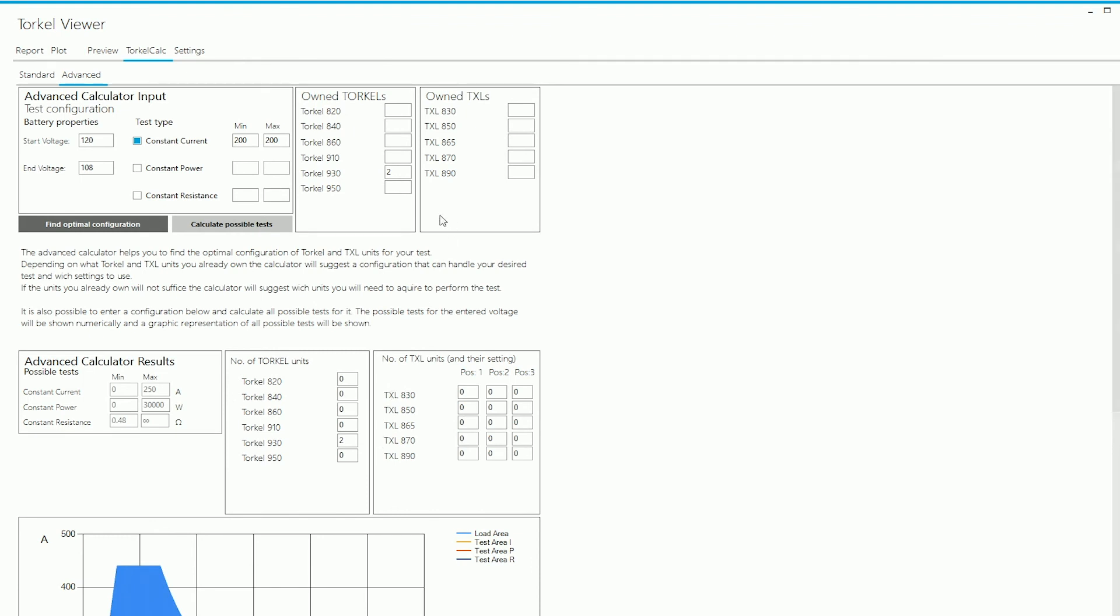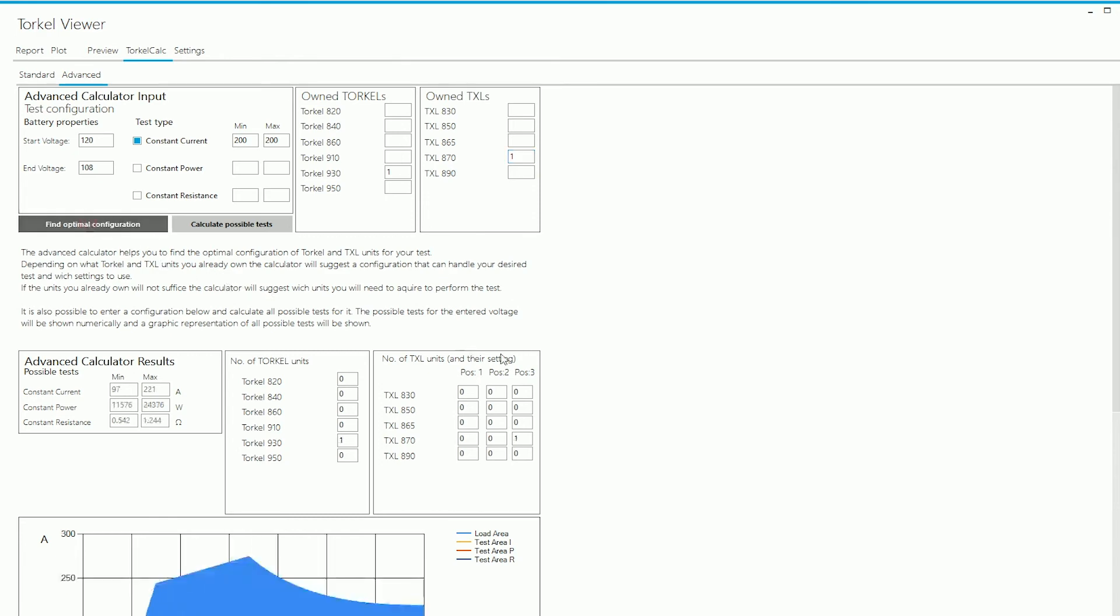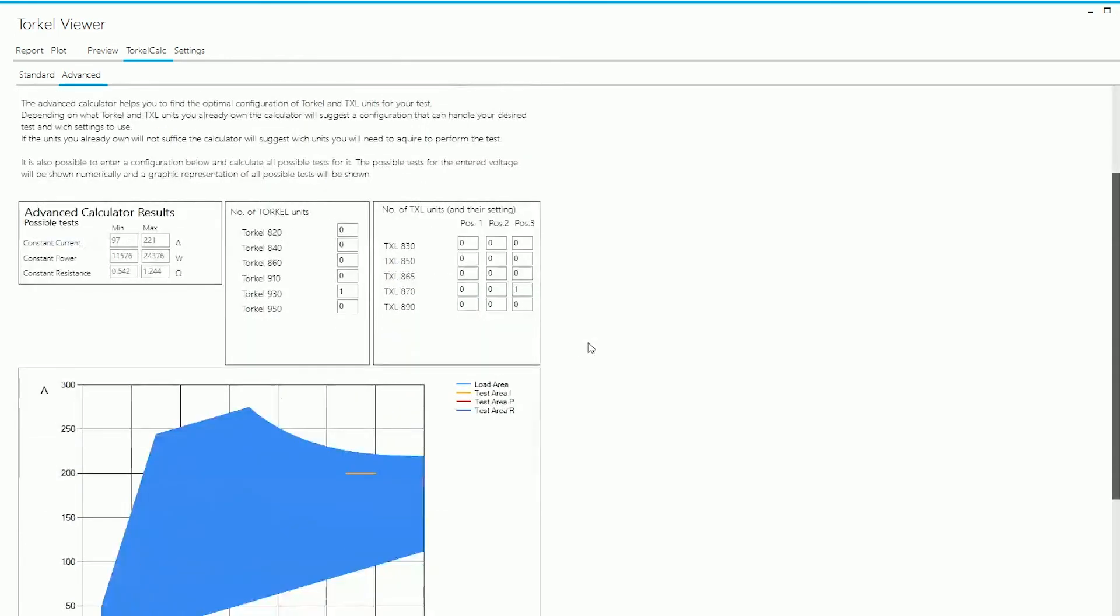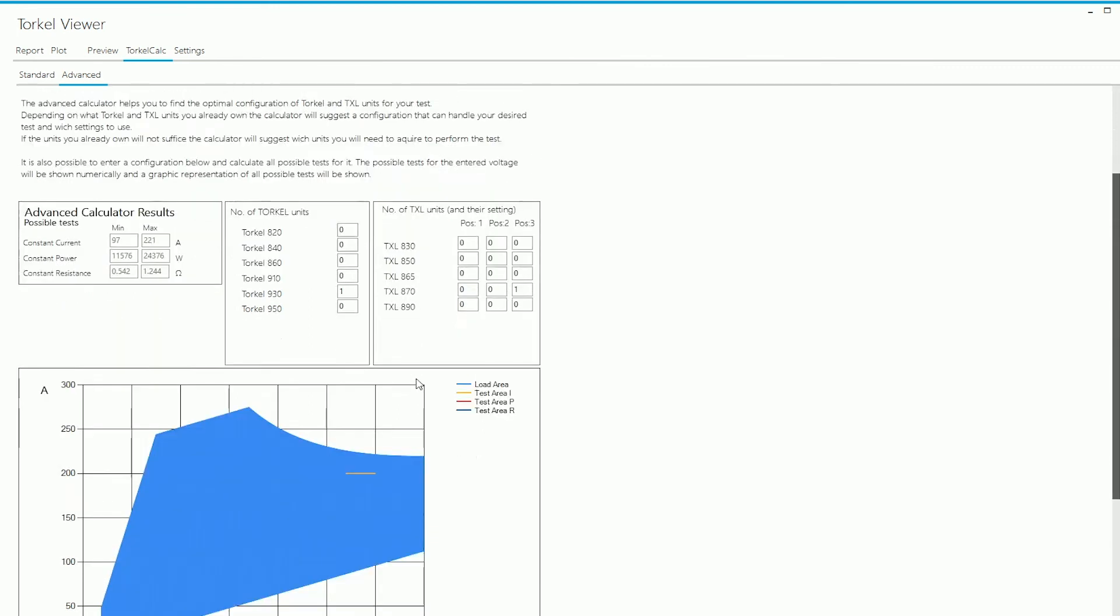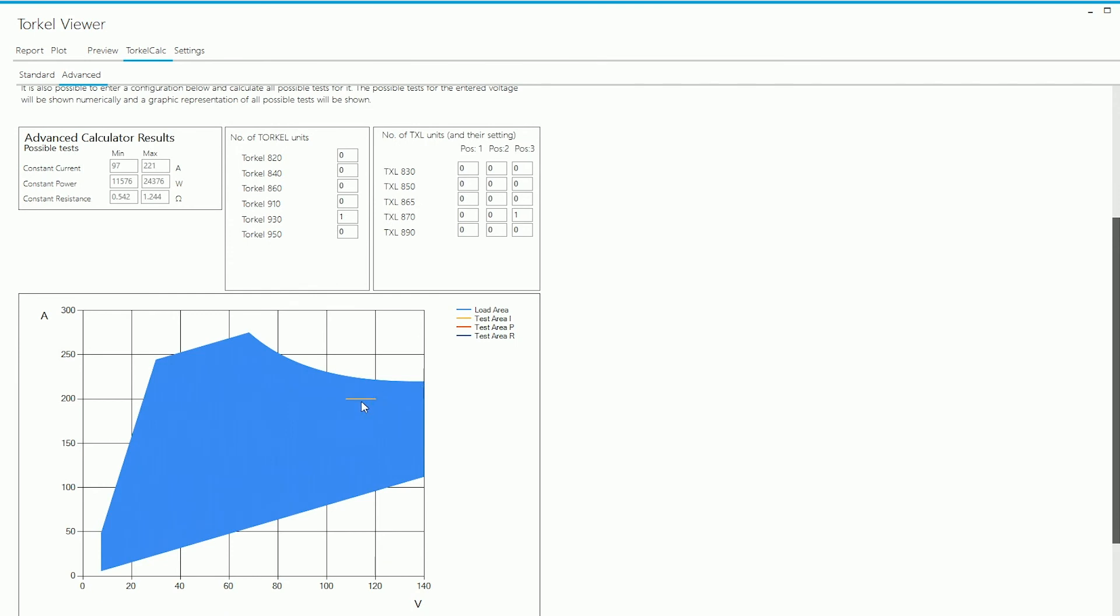Now if you remember when we were in the standard section, the Torkel Calc told us that it's possible to run this test with one Torkel 930 and one TXL 870. Let's select that and see how the calculations change. When you click on Find Optimal Configuration, the software runs the calculations with one Torkel 930 and one TXL 870 and it tells you that it is possible to run the test, but the switch would need to be on position three for you to be able to run the test.